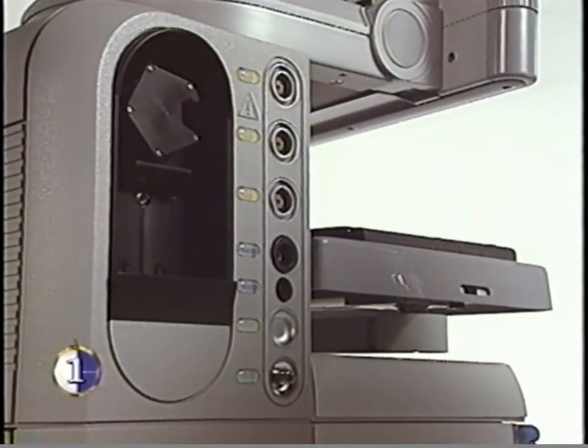The cassette housing on the Legacy's left side panel is designed for quick, efficient loading of fluidics cassette packs. Next to it, you'll connect handpieces for ultrasound, coagulation, autohydrosonics, and anterior vitrectomy on the connector panel. An unlabeled connector is provided for future expansion.